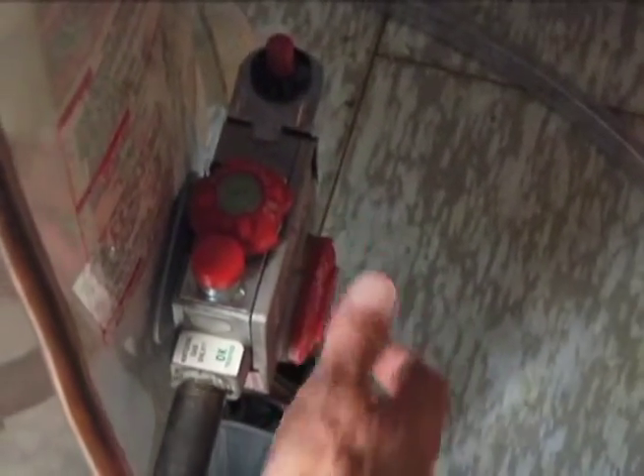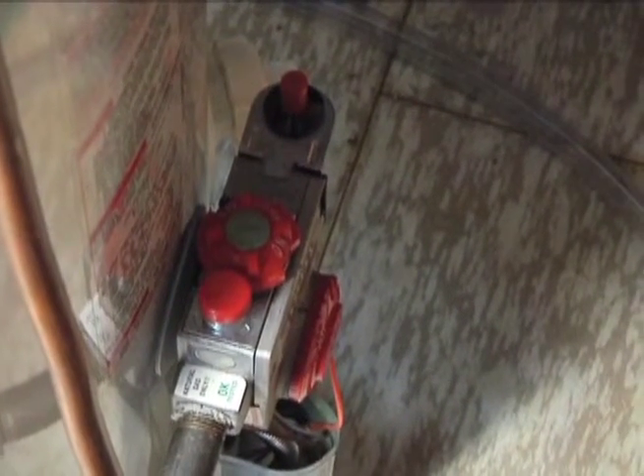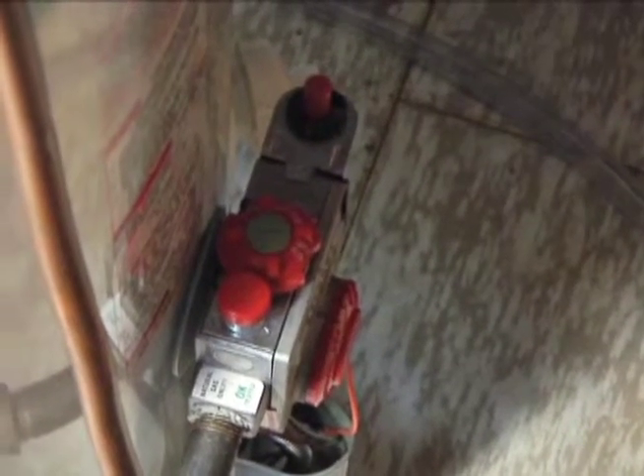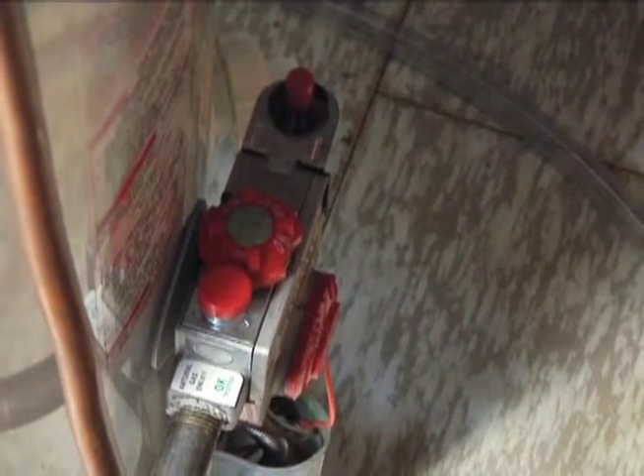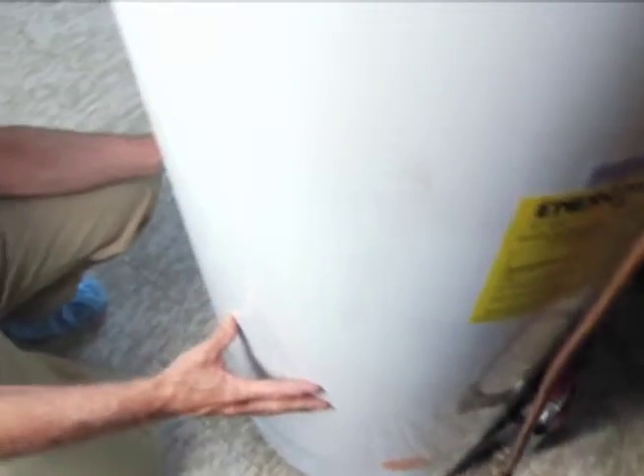As we move around the water heater, you'll also notice there are going to be some gas controls. Good home inspectors will turn the thermostat up, remember what the original setting was, and let the system run. Sit back and listen for a little while — we use our ears too. After maybe 10, 15, or 20 seconds, listen for any noise in the water heater tank. Noise would indicate a buildup of corrosion in the tank. If you find that noise on a particular inspection, it's usually telling us that the water heater is reaching the end of its useful life, and that would certainly be something to mark in your inspection report.